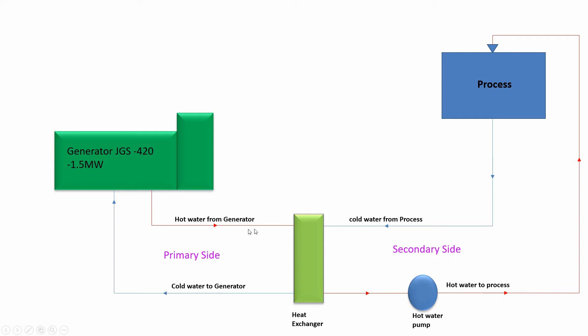Hot water from the generator moves to the after-recovery heat exchanger, where it exchanges heat with the cold water of the process. When its temperature drops, the cold water moves back to the generator to maintain the body temperature of the generator. On the secondary side, cold water from the process moves to the heat exchanger, absorbs heat from the jacket water, and moves back to the process — saving fuel consumption used to heat this process water.